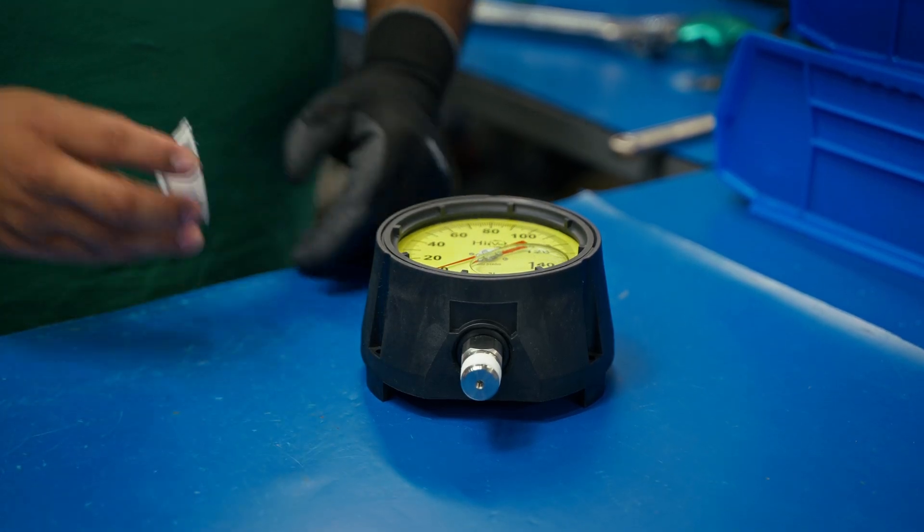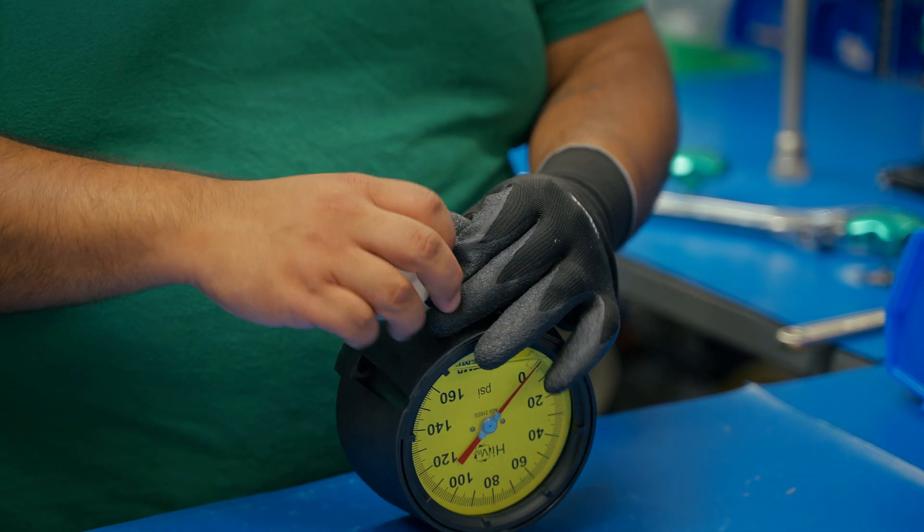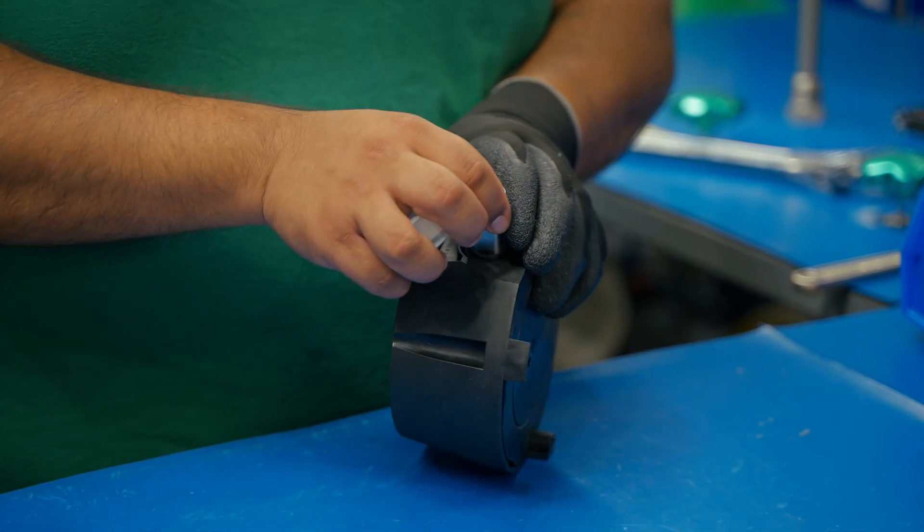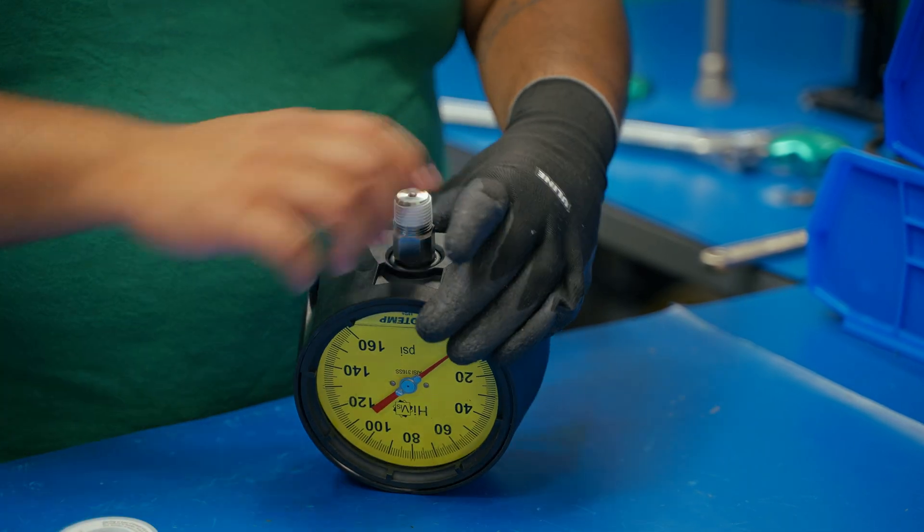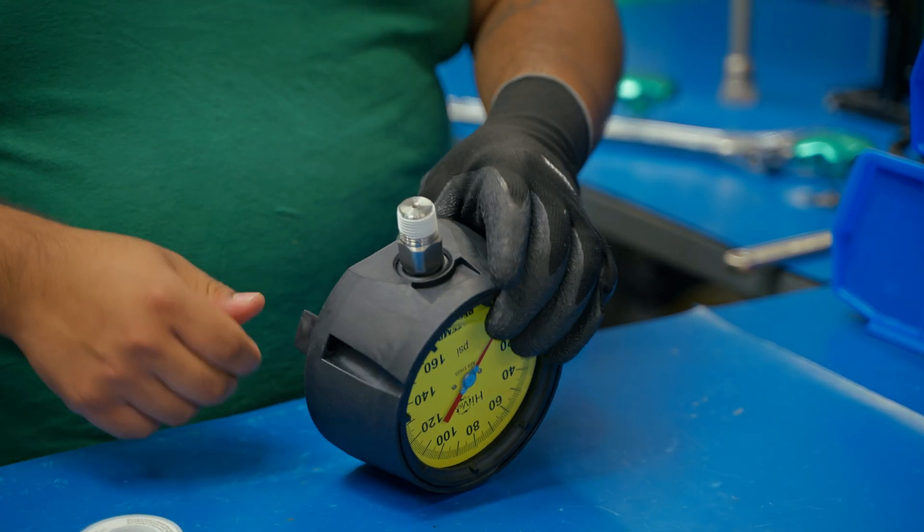Use either Teflon tape or a compatible liquid dope. We're using Teflon tape. Keep the first two threads clean to prevent debris entering the system. Use one and a half wraps starting two threads back.